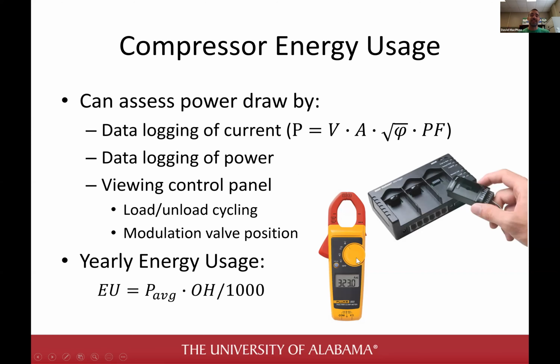You can also use one of these handheld things, which is actually super easy. This is a Fluke meter with Bluetooth, so it hooks up to my phone. Sometimes it's really neat to go up to an air compressor, loop this around one of the three leads, and record a CSV file of amperage on your phone for a couple minutes. You can often get a good idea of how the compressor is used just by monitoring it briefly, especially if plant personnel confirm this represents a normal hour of operation.